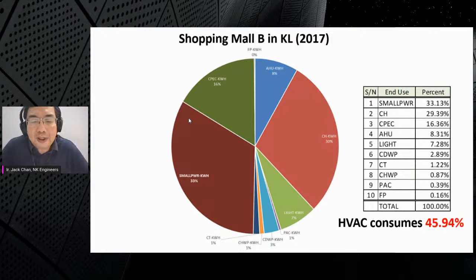From this energy log, you'll also realize that the more divisions are made, the more sectors measured, the more detailed consumption data you get for individual sectors. For example, in this shopping mall, instead of logging the whole plant room, we logged the AHU separately, the chiller equipment separately, and the condenser pump and chill water pump separately. The more individual loggings, the more accurate the data.